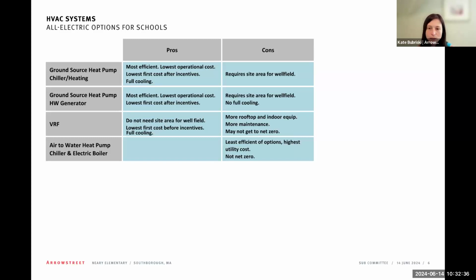More outdoor equipment potentially takes away roof space if you want to have photovoltaics on your roof. It's more that it also is a lot more equipment. Each VRF system is going to handle maybe a wing, one floor of a wing of a classroom bar, so you're going to have more rooftop equipment to maintain. And then the air to water heat pump, chiller, boiler is the least efficient, so it'll obviously have the highest utility cost, and it can't get to net zero. The biggest implication there is utility costs, but also the incentives.